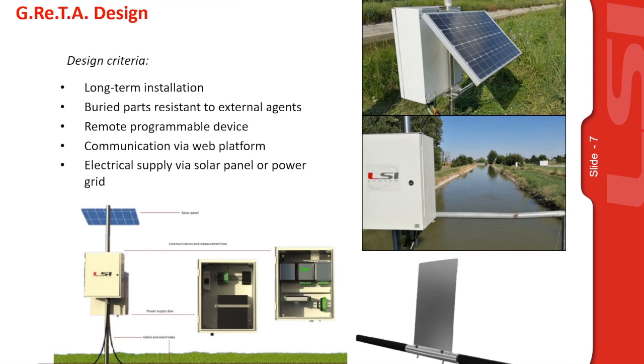The test proved that the ERT method is really effective to understand processes in the levee structure, and the project continued with the design of the GRETA system. The design criteria require that the device be intended for long-term installation — with buried cables and electrodes resistant to external agents, a remotely programmable device, and communication via a web platform. It can be powered by solar panel or power grid. Stainless steel plate electrodes were designed to guarantee good coupling between the soil and the electrodes.